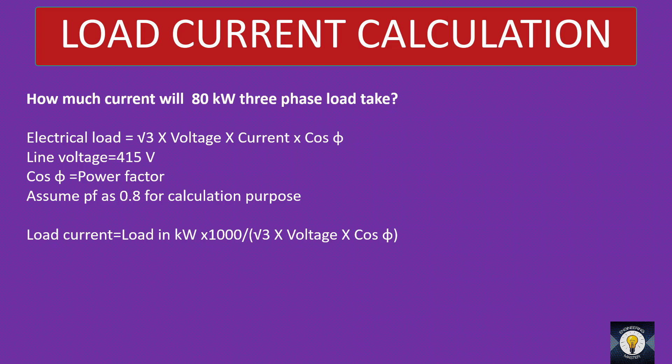There are two practices prevailing in the industry. Some people take the power factor as 0.8, others take it as 0.9. At 0.8 power factor, load current equals load in kW into 1000 divided by root 3 into voltage into cos φ. Substituting the constants — root 3 is 1.73, voltage is 415 V, cos φ is 0.8 — the equation simplifies to load into 1.74. So remember only this value, 1.74, for three-phase at 0.8 power factor.